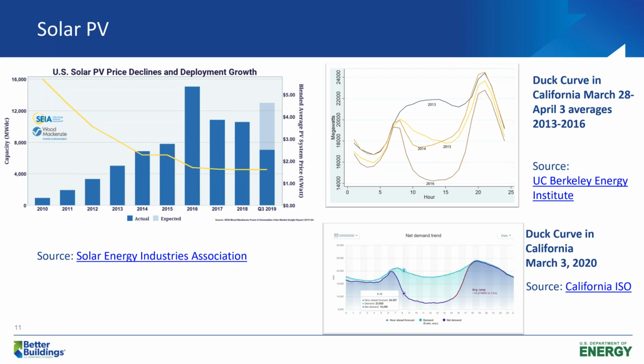It's difficult for the grid to manage this without a fleet of generation resources flexible enough to ramp up and down quickly. Note this isn't a net load of zero on the y-axis—it's 14,000 megawatts, not zero demand, but it's low enough to be hard to manage from a grid perspective. Storage can help mitigate this impact by charging when solar is prevalent.